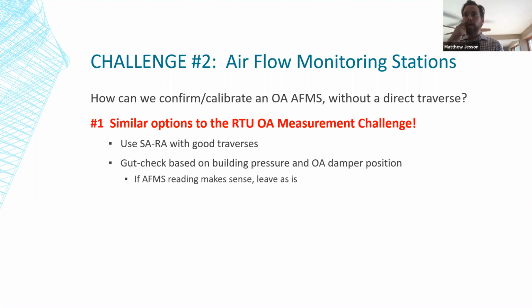And I would also gut check, based on building pressure, outdoor air damper position, or actually we just did this with an outdoor air temperature comparison. And if everything seems to make sense, if the outdoor air damper is 0 to 20% open, building pressure seems in line, mixed air temperature seems to make sense, and you've got a factory installed airflow station, I would leave it reading as is.